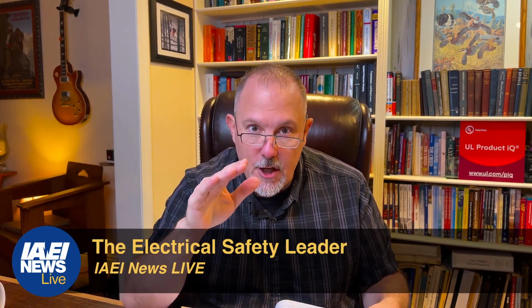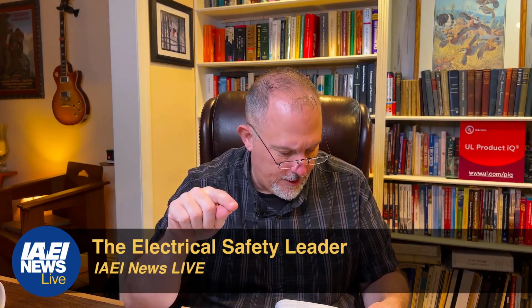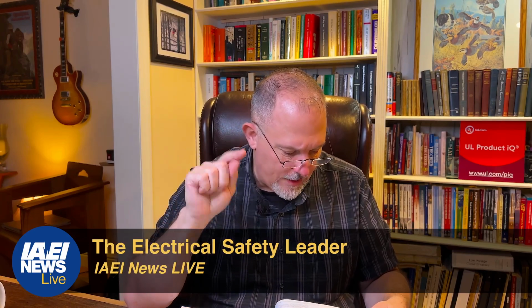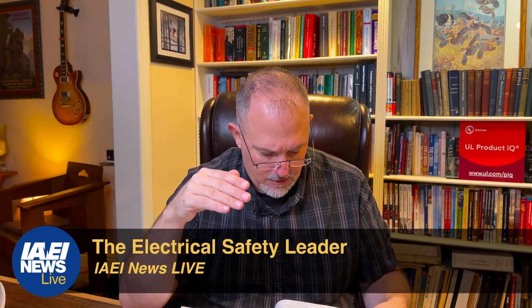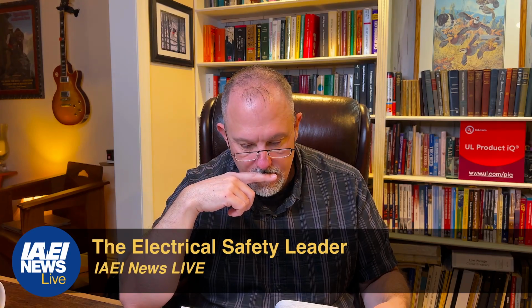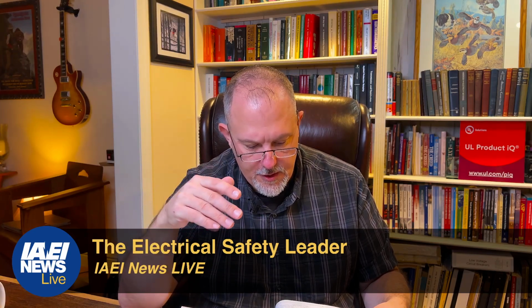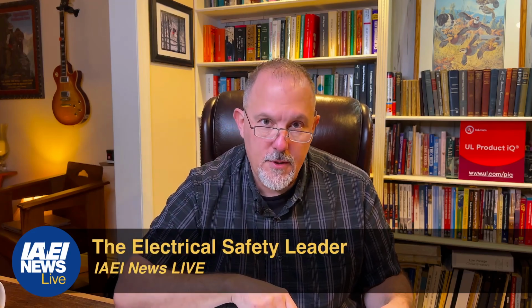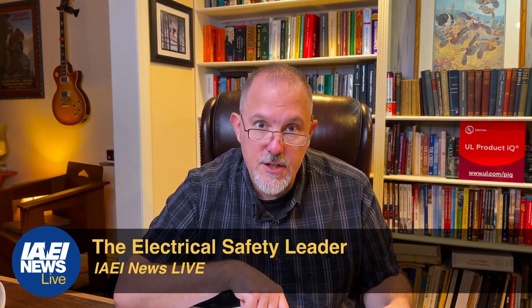404.12, grounding of enclosures. Ooh. 404.13 is your knife switch. 404.14 is rating and use of switches, and there's A through F. So you have your AC general use, you have your AC or DC general use, and CO/ALR: snap switches directly connected to aluminum conductors and rated 20 amps or less shall be marked CO/ALR. Snap switch terminations. Okay, so all of that is in rating and use of switches.